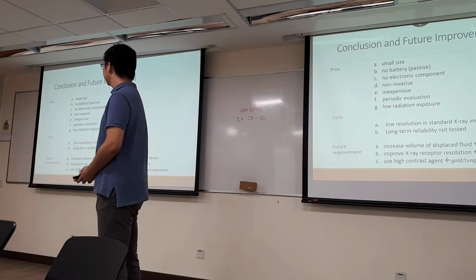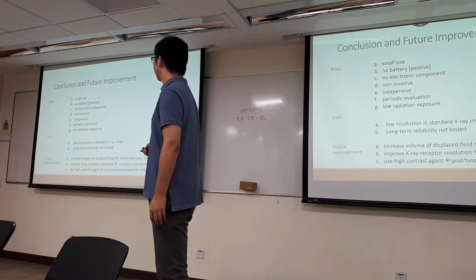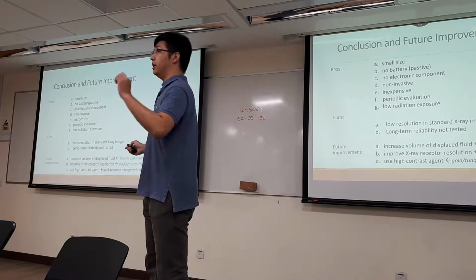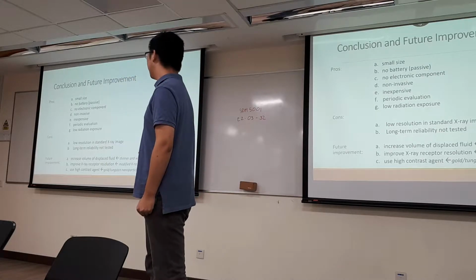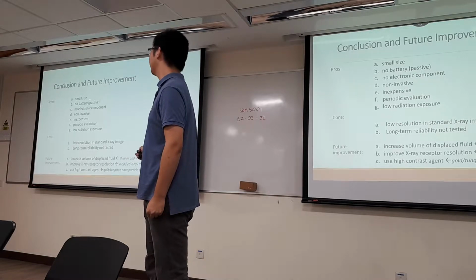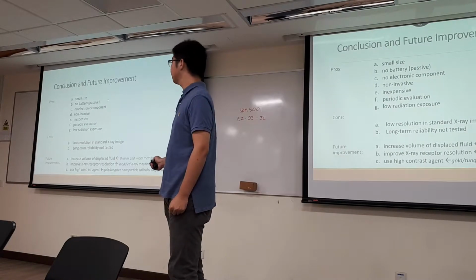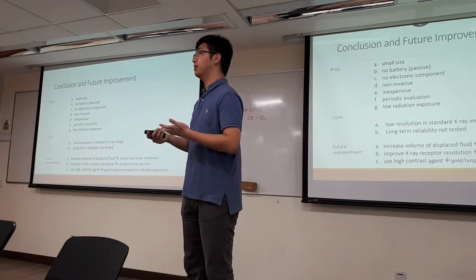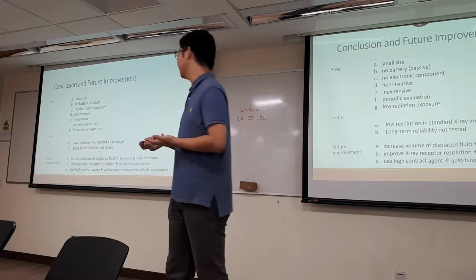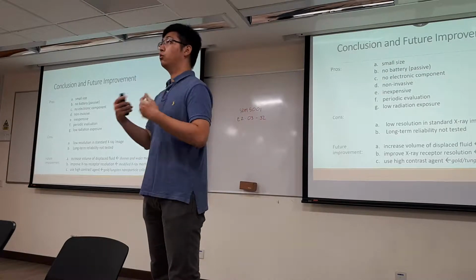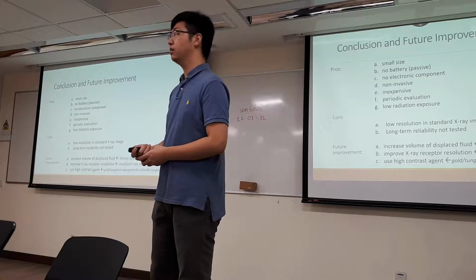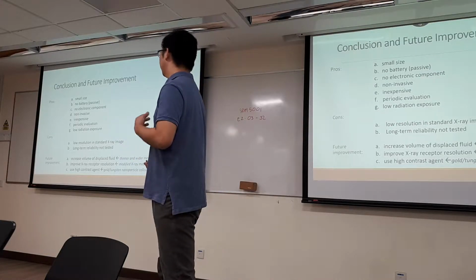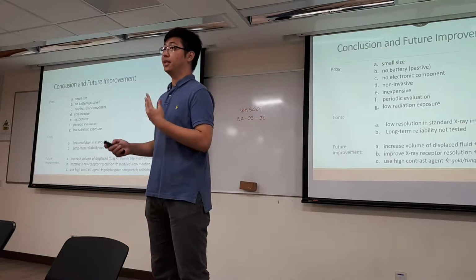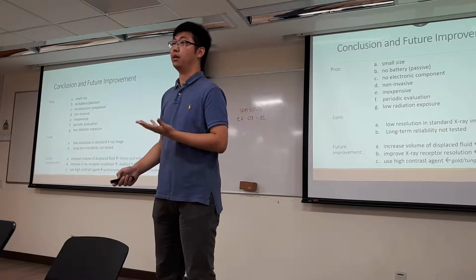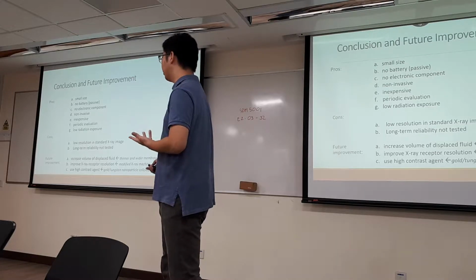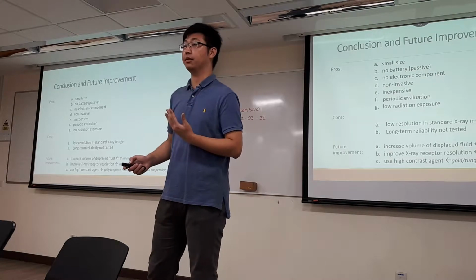So here comes the conclusion. It has a very low-profile probe part. It's very small in size. The width is only 1 millimeter, and it doesn't need any battery. It's a passive sensor. It doesn't need any electronic component, and the monitoring process doesn't need to cut any part of the human body. It's non-invasive. It's not expensive. You just do one X-ray test. It's just maybe $100 or something. And it has relatively low radiation exposure, because compared to CT or other methods, an X-ray test has very low radiation. So that makes it very suitable for periodic monitoring of restenosis.